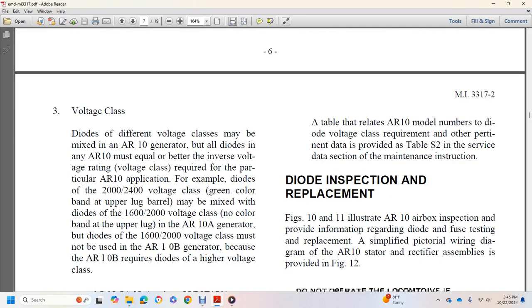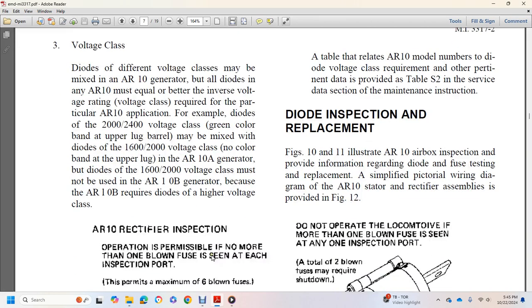Voltage class. Diodes with a different voltage class may be mixed within the AR10. All diodes of the AR10 must equal or be better than the voltage class required for the particular AR10 application. For example, diodes of the 2400 volt class, green color band on the upper lug barrel, may be mixed with diodes of the 1600 to 2000 volt class, no color band on the upper lug, in the AR10A generator. But diodes of the 1600 to 2000 volt class must not be used in the AR10B generator, because the AR10B requires the higher voltage class diode.